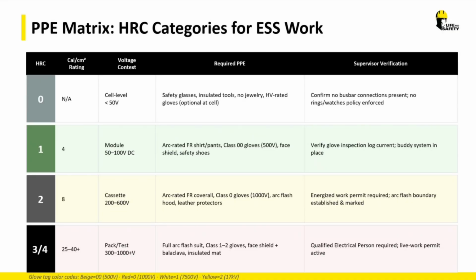So the shock value of the glove is how it's rated, and the class 00 glove is rated for 500 volts AC, 750 volts DC. It's important that people understand we're navigating DC hazards, so the column in the standard that applies to gloves, you want to make sure it's the appropriate column, the DC voltage hazards versus AC. Oftentimes these energy storage systems are interfacing with systems that are inverting or creating an AC waveform.